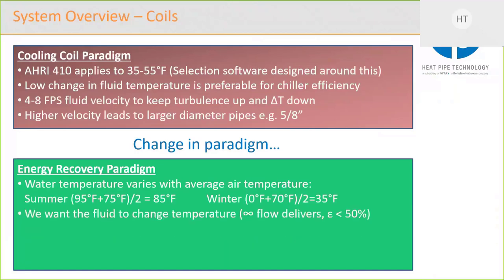The other thing is we want the fluid to change temperature. And why is that? So if you think of a thought experiment where you have an infinite flow of liquid, then your heat capacity is infinite. So your water won't change temperature. But if your water doesn't change temperature and its temperature is the average air temperature between the two air streams, then you can never get an effectiveness bigger than 50%. So having too much fluid flow is actually a problem. It actually limits your effectiveness to 50% or less.